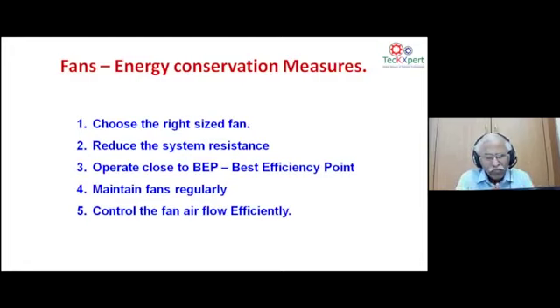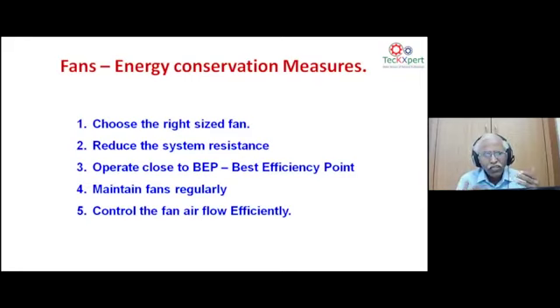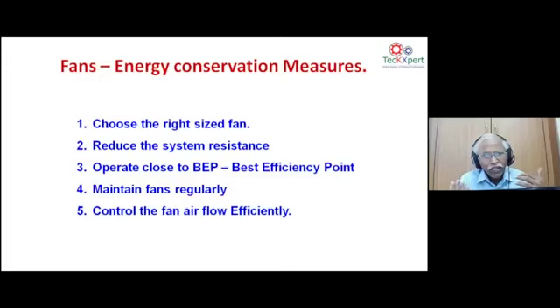Right-sizing: many industries have oversized blowers — for example, specifying a 5.5 kW blower but only operating at 2 kW. Oversizing itself is a system loss. Second is system resistance — the static pressure in pascals at the downstream of the blower must be maintained and optimized. Third, any blower purchased needs a fan performance curve from the OEM, just like a test certificate for a transformer, to identify the best efficiency point.